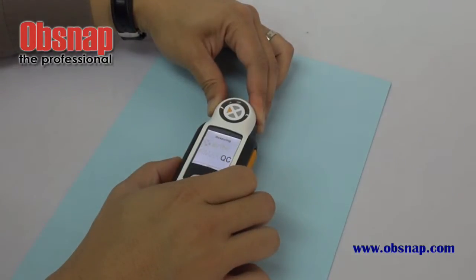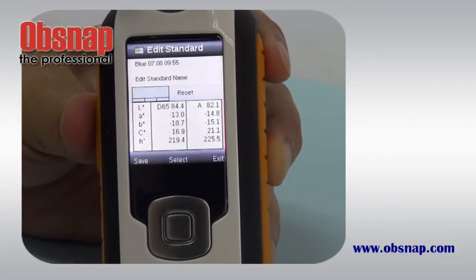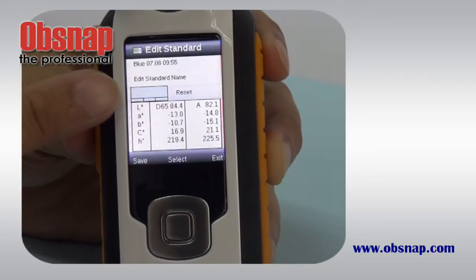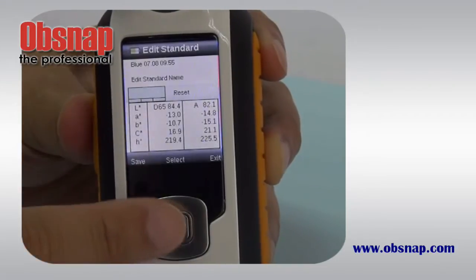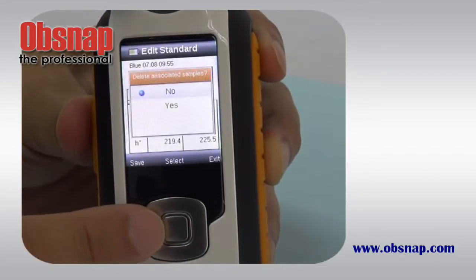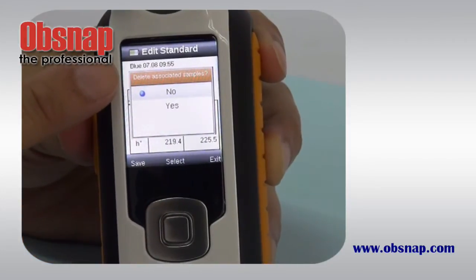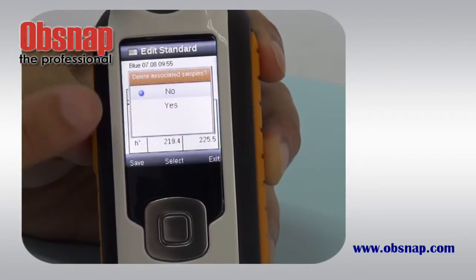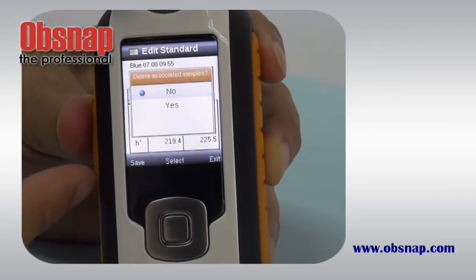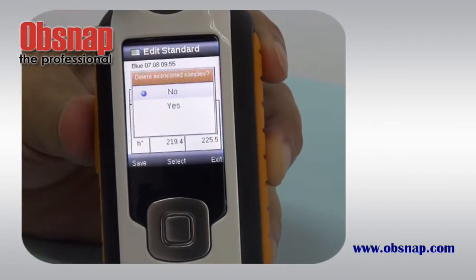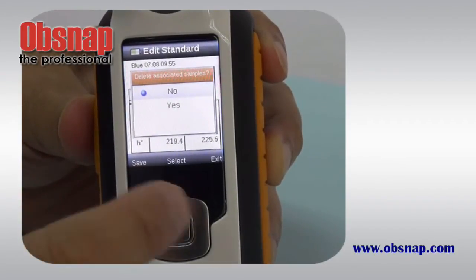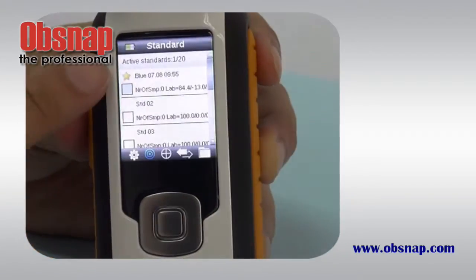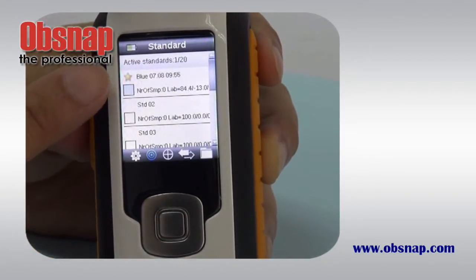1, 2, 3. Once we have done the 3 measurements, the unit will automatically calculate the average value of LAB for us. Then we press the save button. It will ask us to delete associated sample. If we have a sample installed into this standard that we want to delete, we press yes. If no, then we can just press no. The new standard has been set.